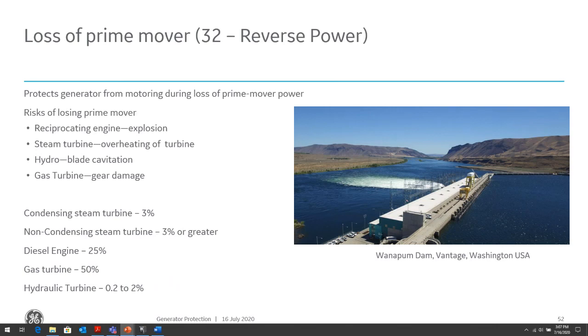The reverse power element is used to prevent this condition. The reverse power element basically looks at the motoring condition where the generator is seeing power go in the reverse direction, so it will detect that condition. And usually this reverse power element is set for sequential tripping, so that the power is backed off until we're importing a little bit of power, so as not to trip while the system is exporting power and go into an overspeed condition. If it's exporting power, we don't want to trip right away because that's considered a load rejection. We can go into an overexcited, overspin condition. So we want to back off the power a bit until we get slightly into importing power and then trip for that condition. And so we refer to sequential tripping.